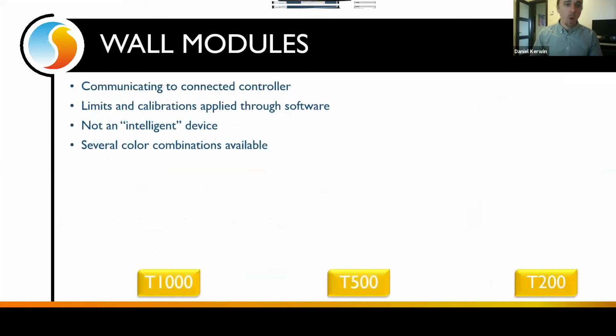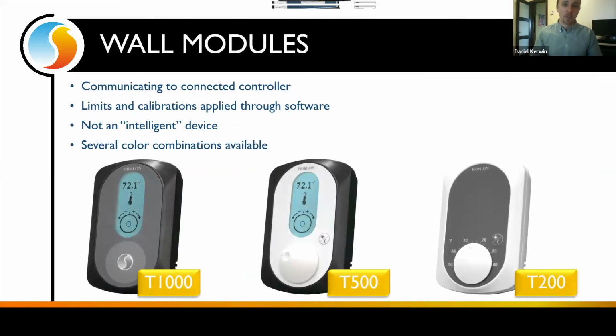We have different wall sensors with these devices. So there's the entry-level T200. There's the mid-level T500, which has the digital display and the adjustment knob. And then there's the T1000, which has the digital display, and it actually has a touchpad on it. What differentiates the T1000 a little bit more is that you are able to access the VAV settings from this wall module. So you can configure an entire VAV controller through the menus of the T1000.